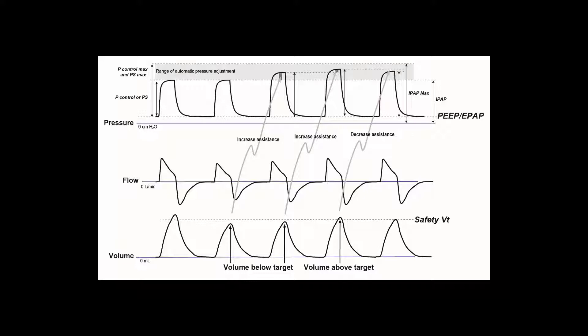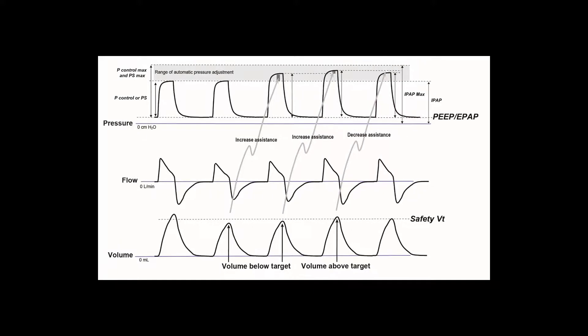Safety Tidal Volume is a supplementary feature of the Astral device. When used with a pressure support mode, it is a volume-assured pressure support, or VAPS mode. This feature allows the clinician the flexibility to use a standard vented mask — for example, pillows or nasal mask — with Astral. Because you will be using a standard leak circuit, you can expect enhanced leak compensation as well as fewer ventilator alarms.